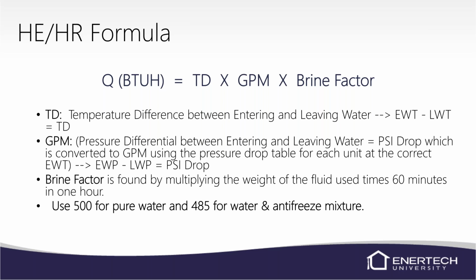use the 500. Or if you've oversized your loop, so you're down in Florida and you don't have to worry about water freezing, then you can use no antifreeze in a closed loop. But if you anticipate your water temperatures are going to get to 40 degrees or a little bit below, anything below 40 degrees, you must put antifreeze in our system or in the water circuit, because it will freeze. Anything can happen, a contactor gets stuck, whatever. But at that 40 degrees, you could also be leaving at around freezing.